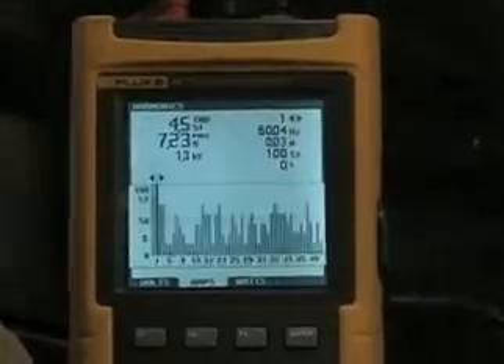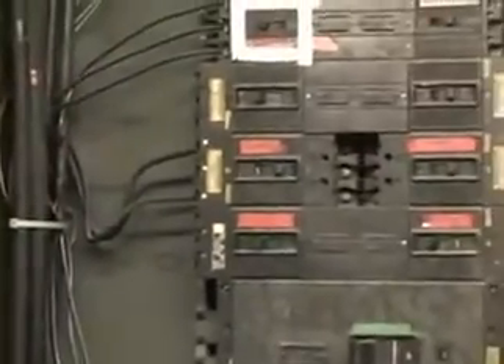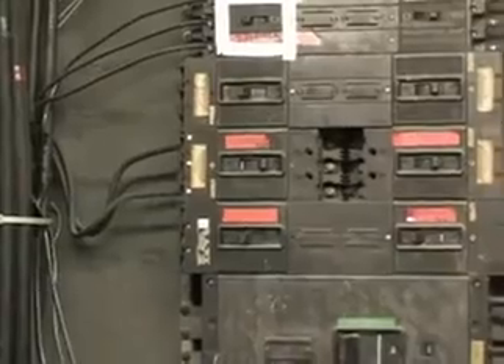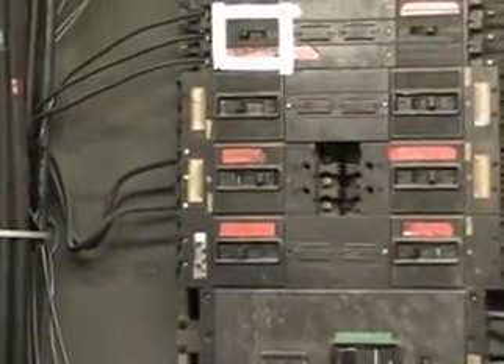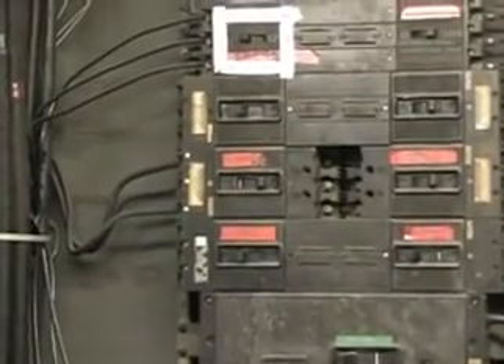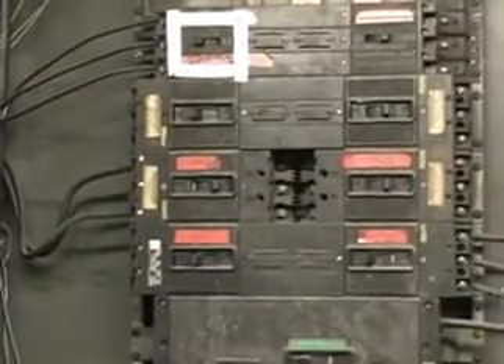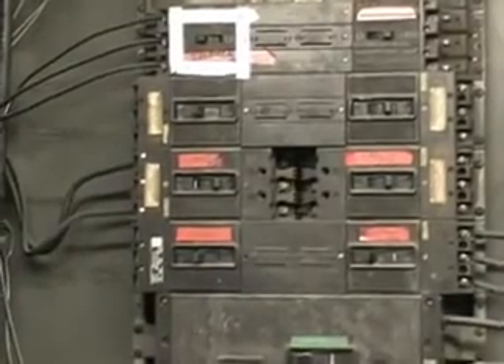So what do these readings indicate? We know that this breaker is 70% loaded and we have a low harmonic distortion. This means that the harmonic distortion is not generating any significant amount of heat. The actual heat on the breaker is between 35 and 39 C, which is within the acceptable operating parameters. If we rely on infrared thermography alone, we would have determined that this breaker is under normal load and generating an acceptable level of heat.